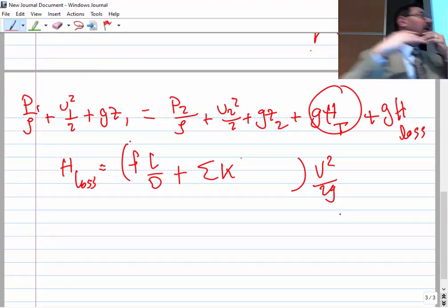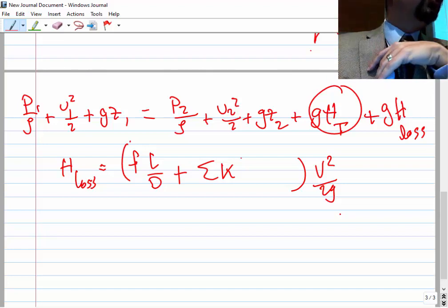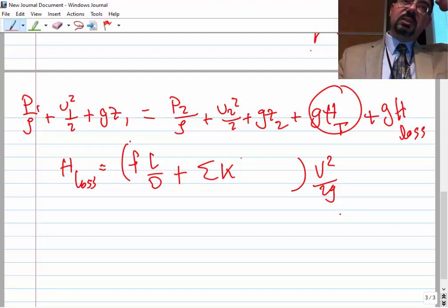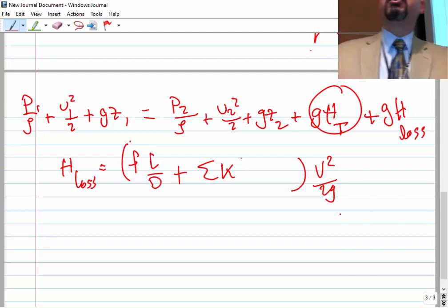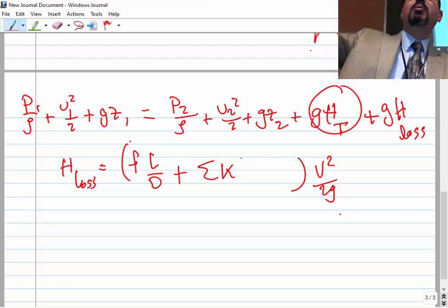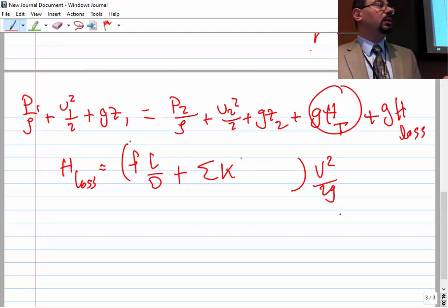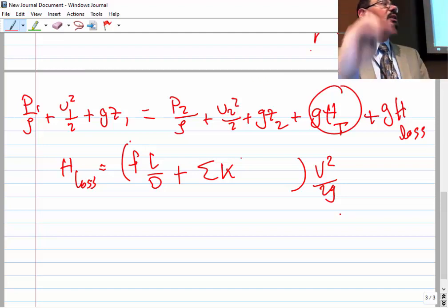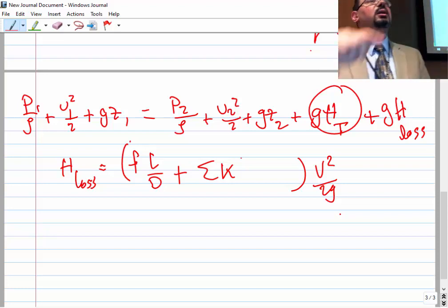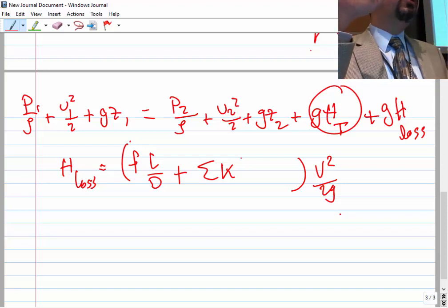So if you open a manual or textbook for all those minor losses, our textbooks say one of the best is the Crane Company Report 410, which has a compilation of all different valves and different elbows, and they will express them in K.